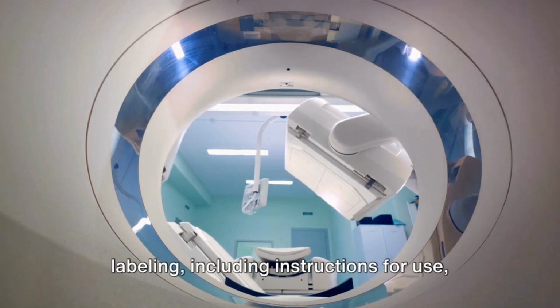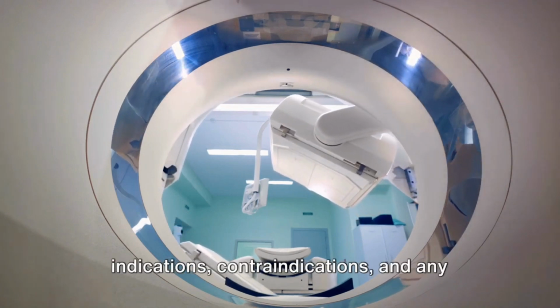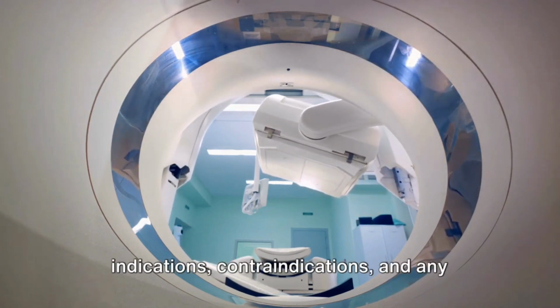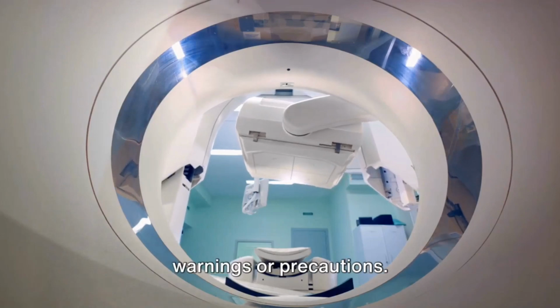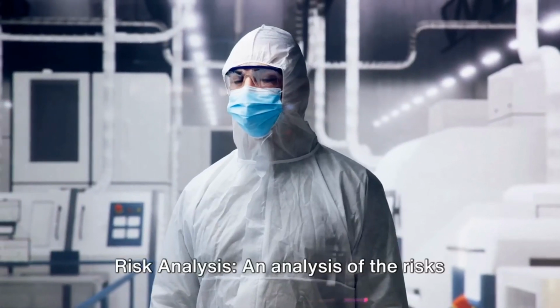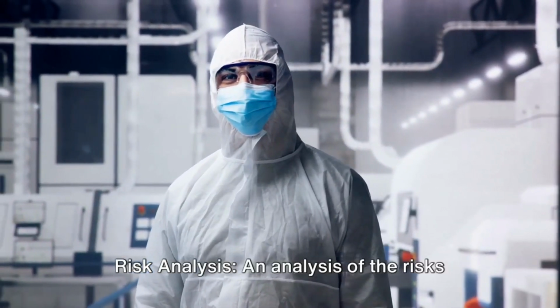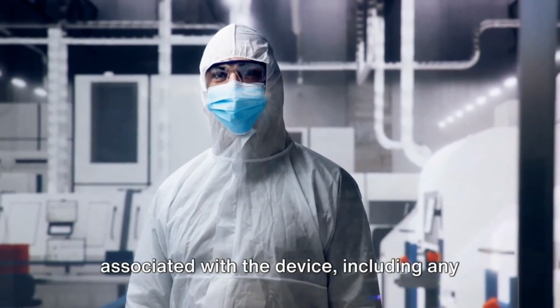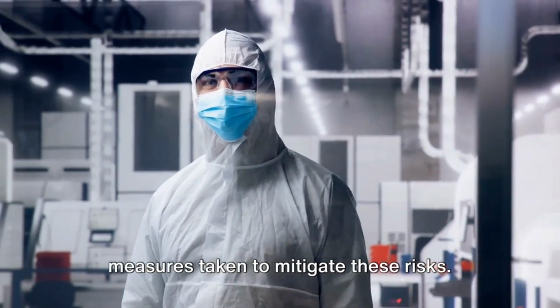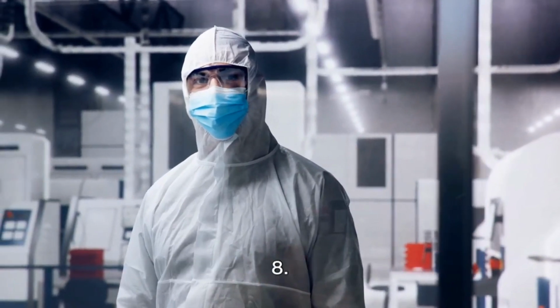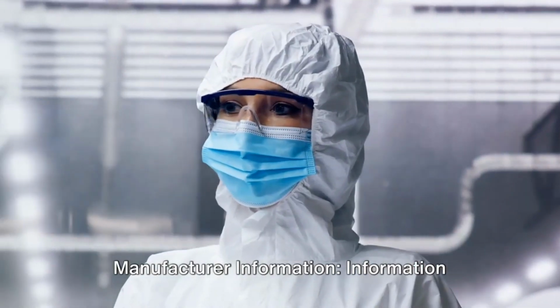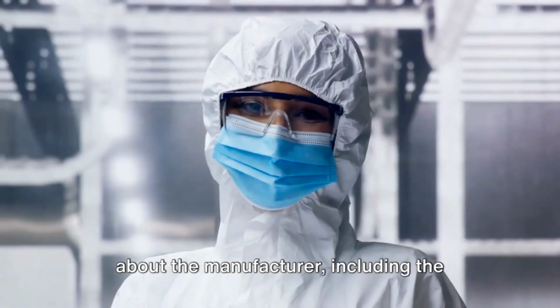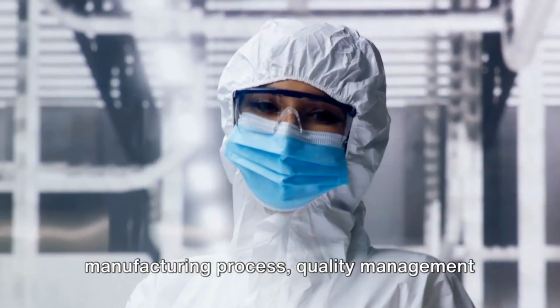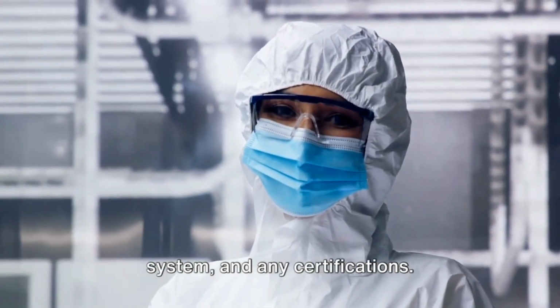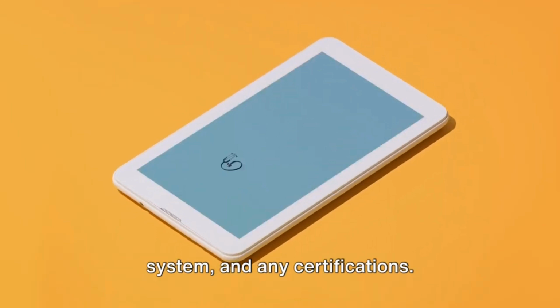Copies of the device labeling including instructions for use, indications, and any warnings or precautions. 7. Risk analysis. An analysis of risk associated with the device, including any measures taken to mitigate this risk. 8. Manufacturer information. Information about the manufacturer, including the manufacturing process, quality management system, and any certifications.